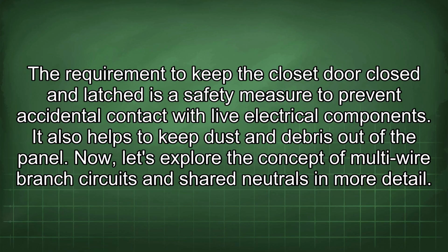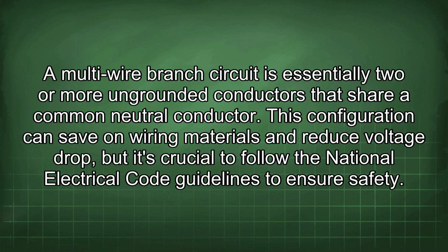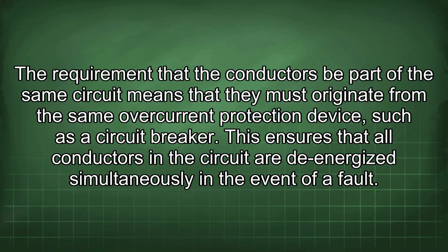Now let's explore the concept of multi-wire branch circuits and shared neutrals in more detail. A multi-wire branch circuit is essentially two or more ungrounded conductors that share a common neutral conductor. This configuration can save on wiring materials and reduce voltage drop, but it's crucial to follow the National Electrical Code guidelines to ensure safety. The requirement that the conductors be part of the same circuit means that they must originate from the same overcurrent protection device, such as a circuit breaker. This ensures that all conductors in the circuit are de-energized simultaneously in the event of a fault.